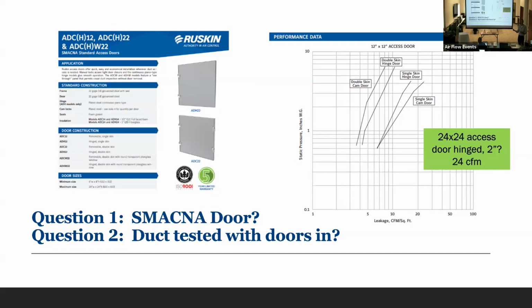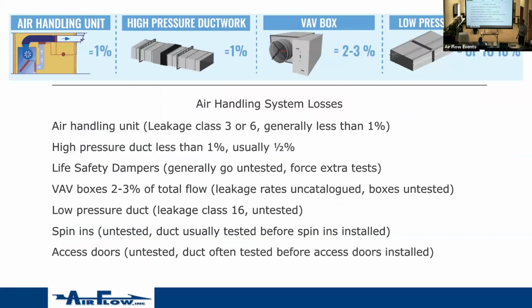The access door doesn't cost $100, but it leaks $100 worth at least every year. Okay. Looking at the system, we know that the air handler leaks. If it's a custom air handler, it might be 0.5%. If it's a modular air handler, it might be 1%. Air handlers have their own leakage tests. We're not covering it here.